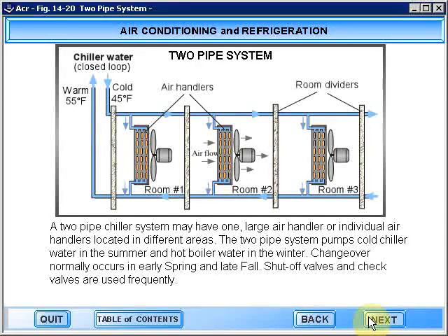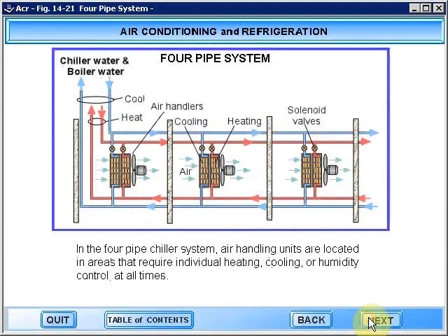A two-pipe chiller system may have one large air handler or individual air handlers located in different areas. The two-pipe system pumps cold chiller water in the summer and hot boiler water in the winter. Changeover normally occurs in early spring and late fall. Shut-off valves and check valves are used frequently. In the four-pipe chiller system, the air handling units are located in areas that require individual heating, cooling, or humidity control at all times.